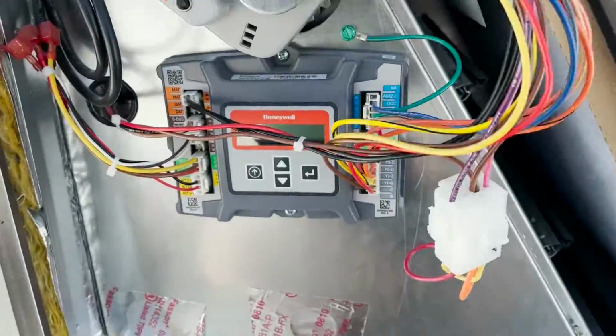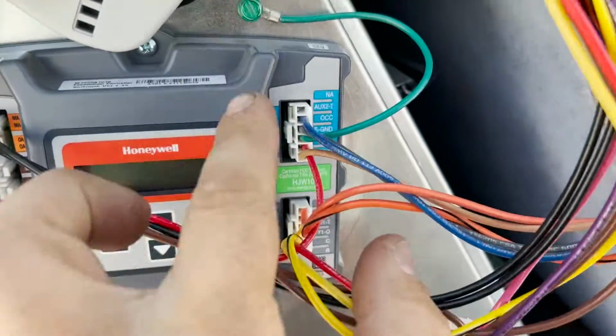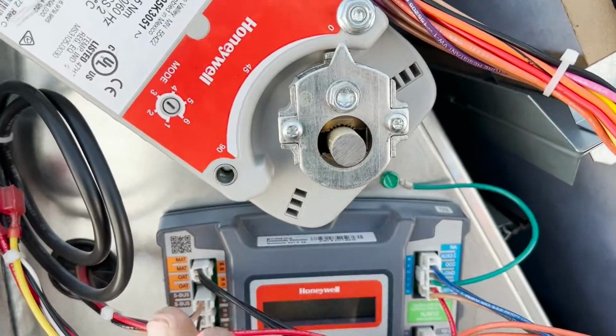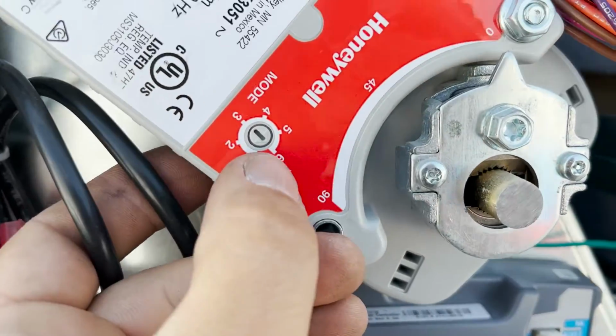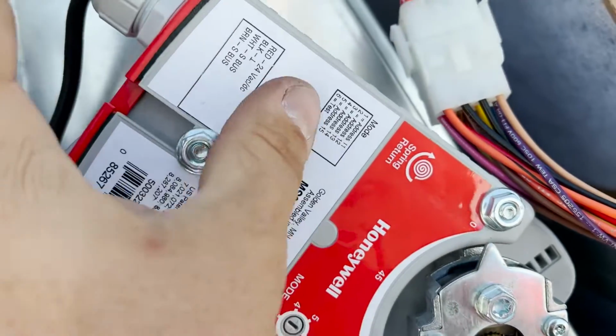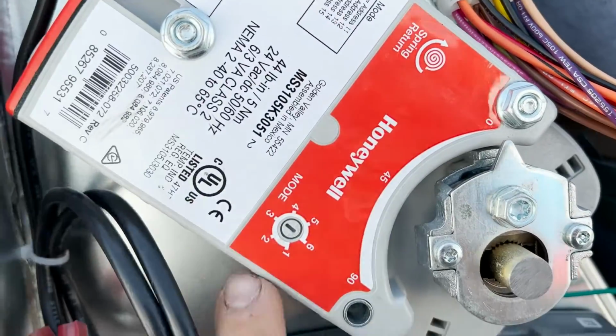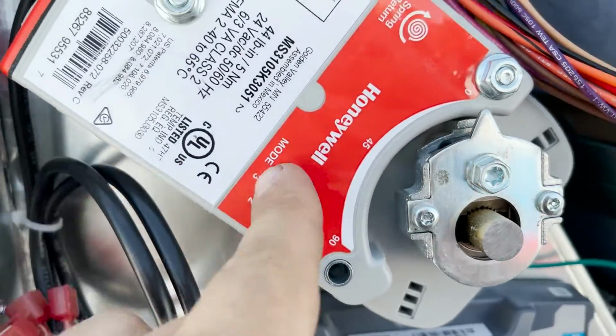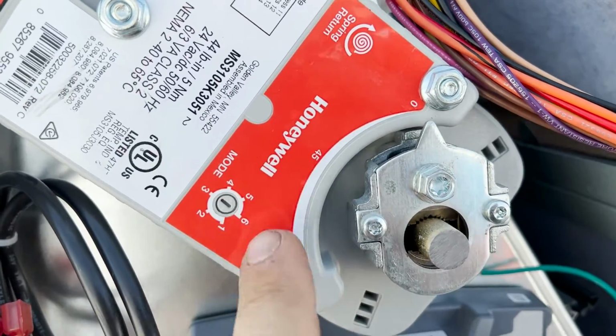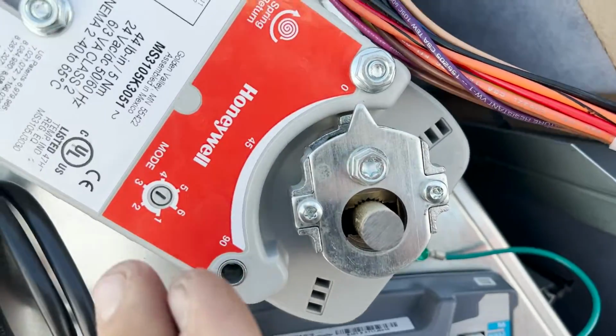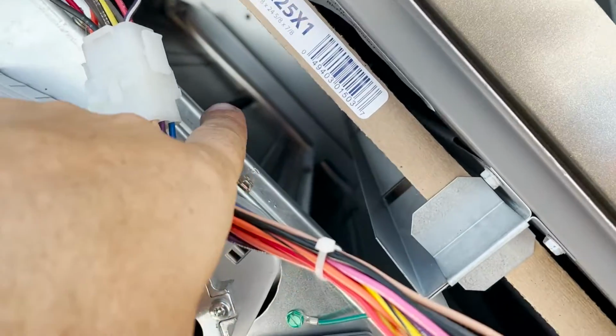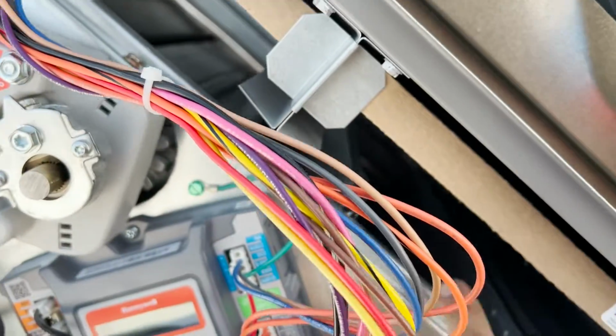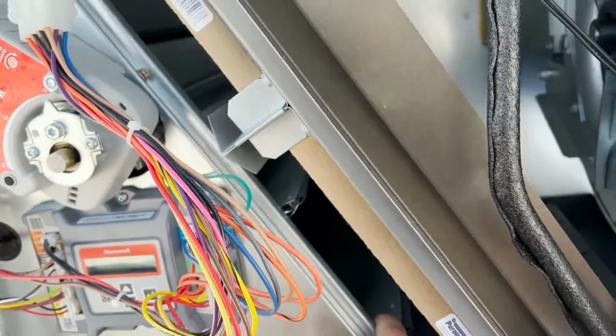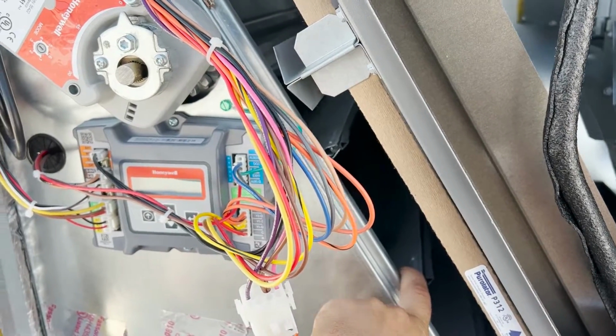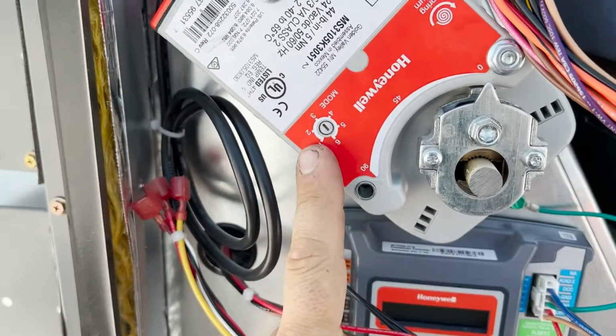This one's kind of tight. I don't know what happened. These needed plugged back in. And then on this batch, I don't know why they're doing this. 6 is test mode, okay? This needs to get moved back to number 1. If you start it up like this, it'll be fine, but it's gonna open the outside air damper 100% and close the return air 100%. So you're gonna get weird numbers if you don't put your economizer into the right mode.